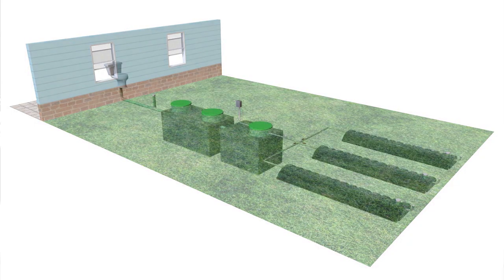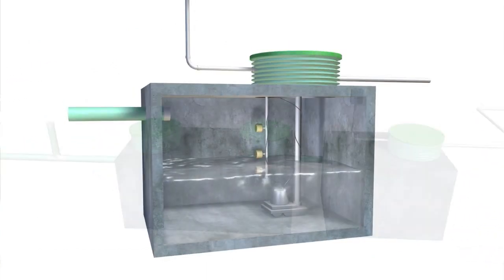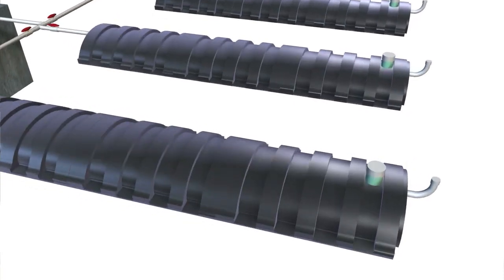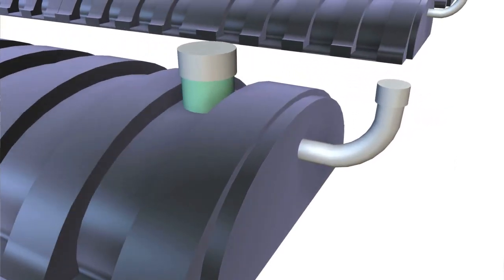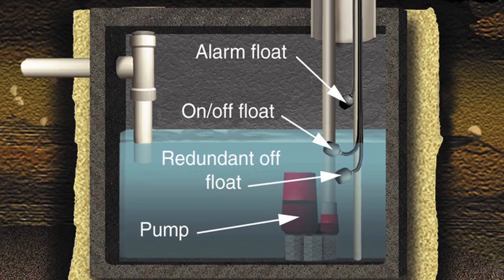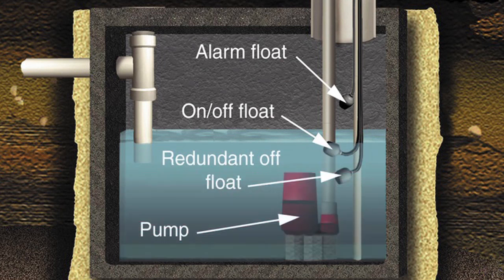Pressurized systems start with a septic tank just like a gravity system. After the septic tank, the wastewater flows into a pump tank and is pumped to the drain field, where it's spread equally throughout the drain field lines. The pump tank accepts wastewater from the septic tank through an inlet baffle. The pump itself is located on the floor of the tank. There are two floats used to control the pump: the on/off float and the redundant off float. If the wastewater level were to drop below the pump, the pump could overheat and burn up.